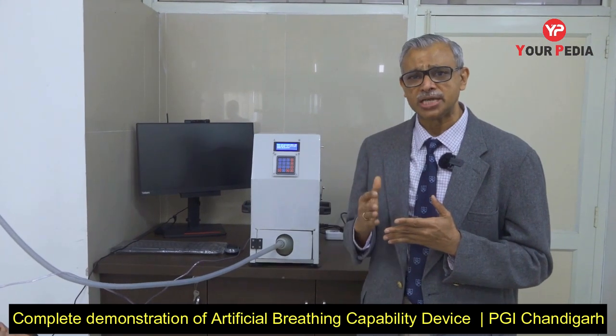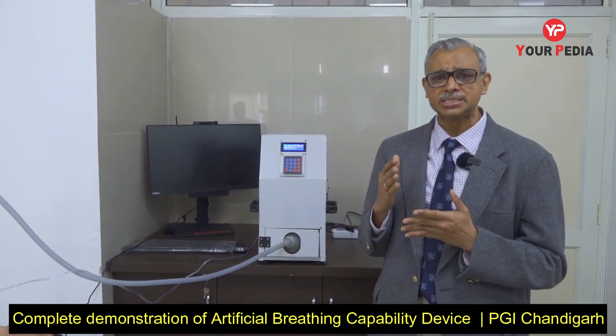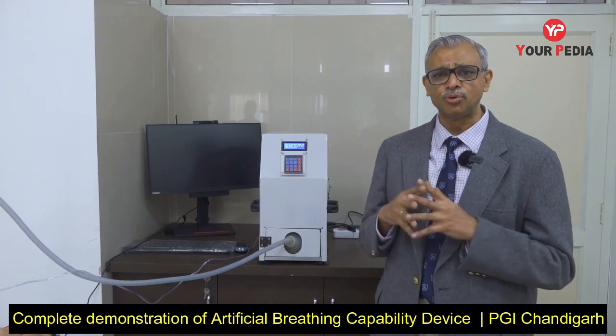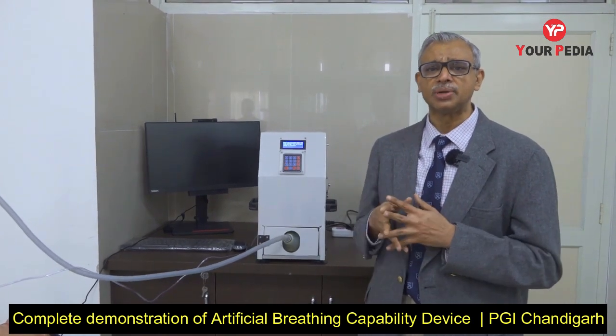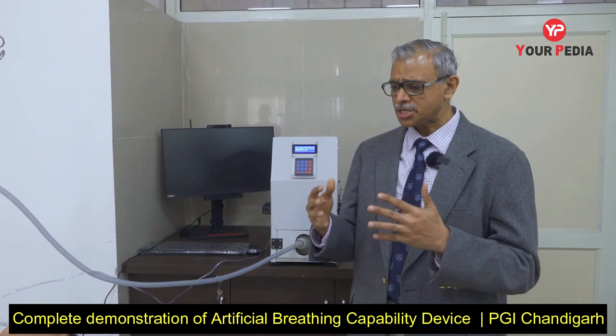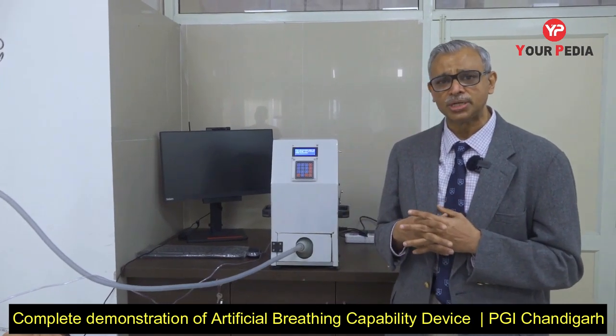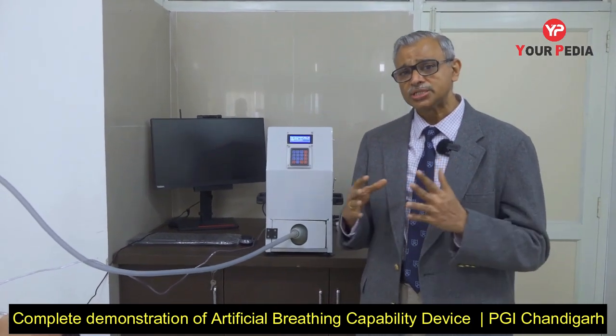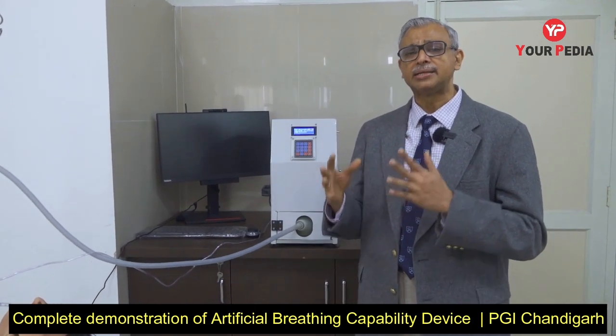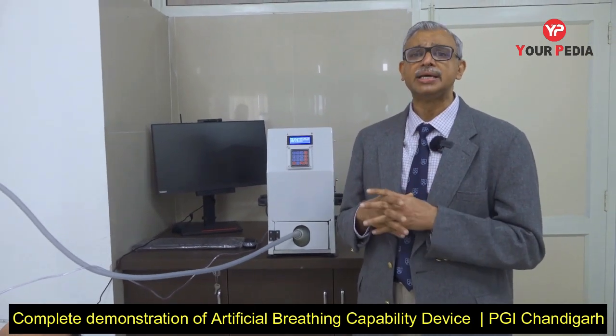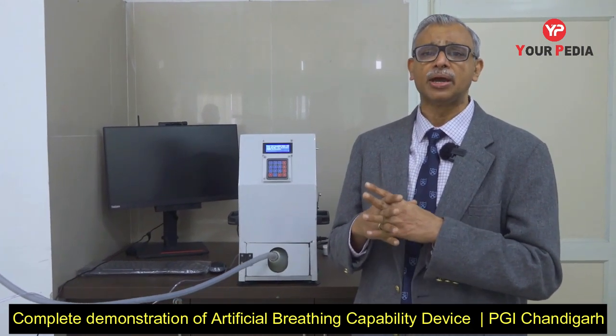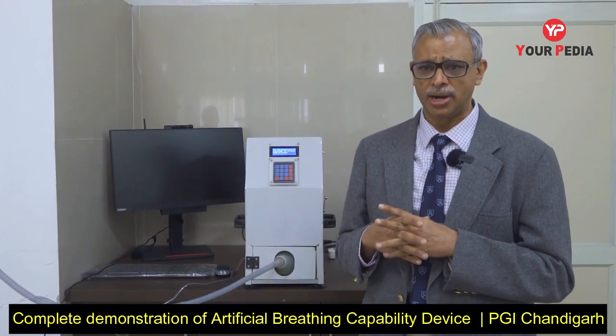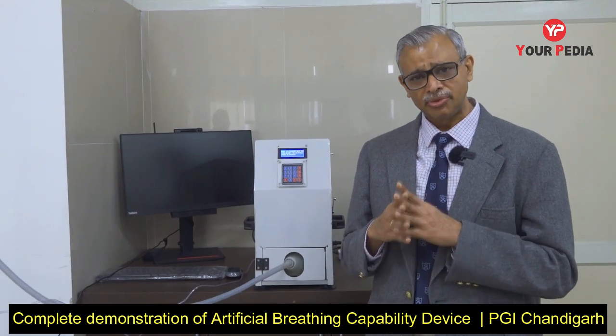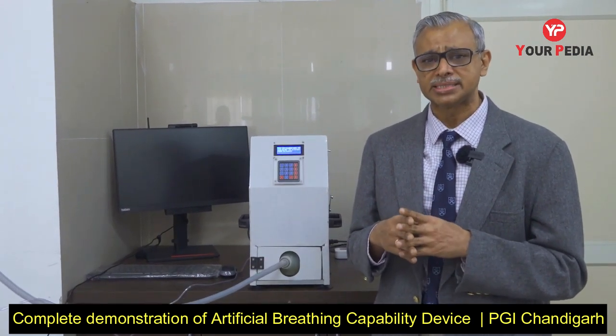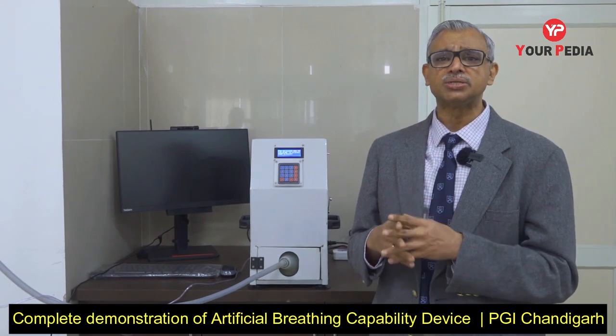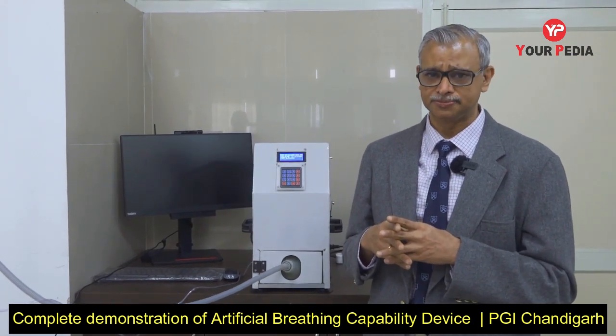This is the only device which has been clinically tested in an emergency care setting under an ethics approval of the PGIMER, and then subsequently has been commercialized. The commercial company provided initially 5 to 10 units of this device, but not fit to release directly into the market until we have lab tested and verified that they are performing in accordance with the clinical specifications required. Now, those lab tests are underway right now, and we are hopeful that in the next 30 to 60 days, these units will then be available commercially in the market.